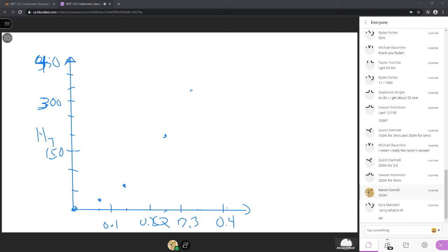And so I end up with a system curve, which looks remarkably like the system curves that you created in your lab. When we look at this particular system curve, the first thing we'll notice is that it starts at 0 meters of head. That means there are no static head requirements for this pump. When the flow is not happening, this pump does not have to put any energy into the system. All of the requirements of this system come in terms of the dynamic head, or head that's moving.